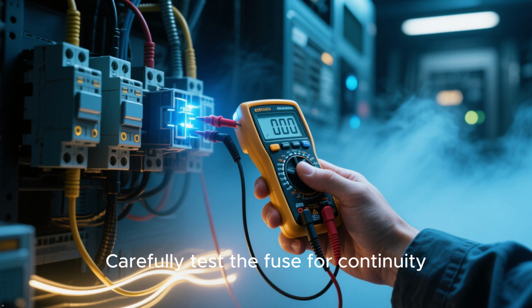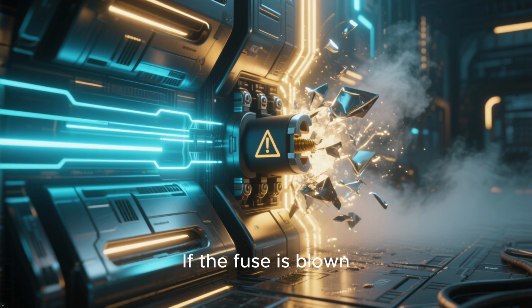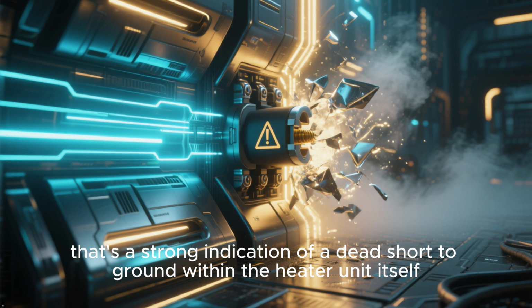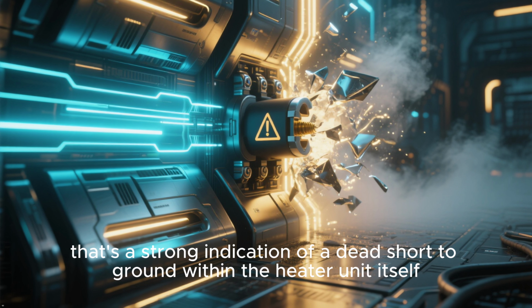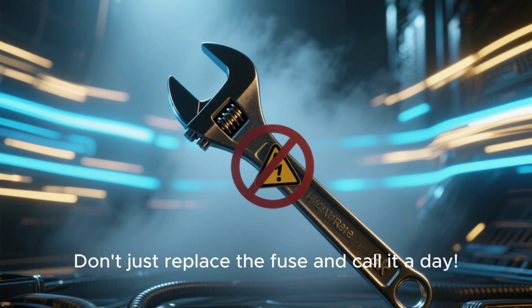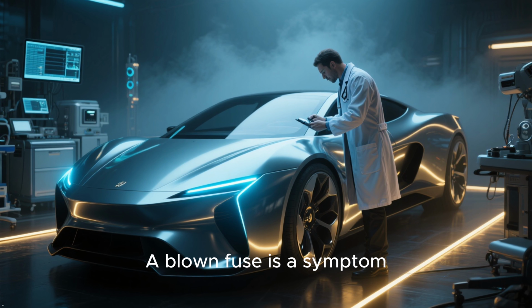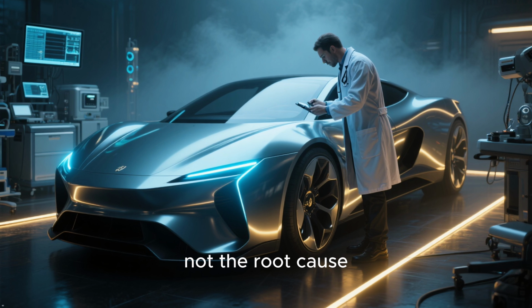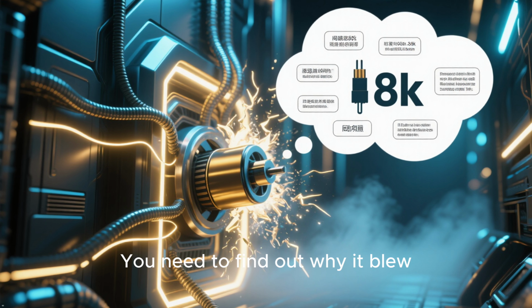Carefully test the fuse for continuity. If the fuse is blown, that's a strong indication of a dead short to ground within the heater unit itself. Don't just replace the fuse and call it a day. A blown fuse is a symptom, not the root cause. You need to find out why it blew.